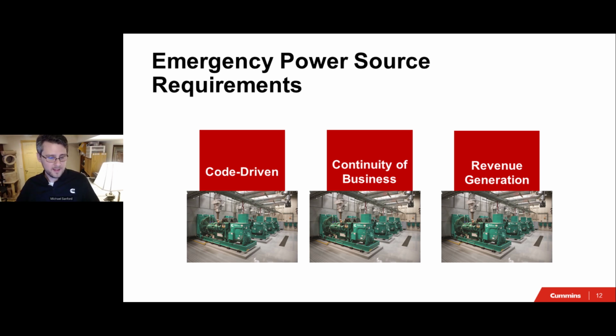That site falls into all three buckets I talked about. It's code-driven in the sense that those generator sets cover the life safety and legally required loads of that facility, but I promise you that's nowhere near the 5 megawatts of total capacity on site. That's there because of continuity of business—even during a failure of the normal source, that facility wants to keep operating for the duration of the outage so we can keep products moving down our production line.